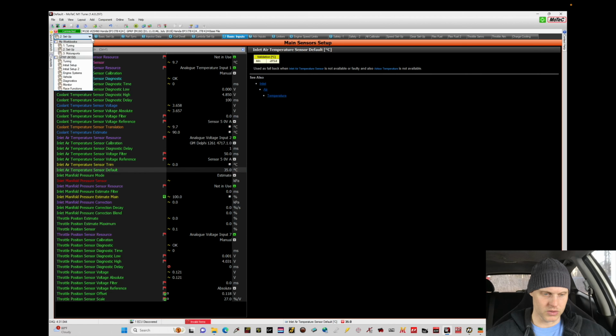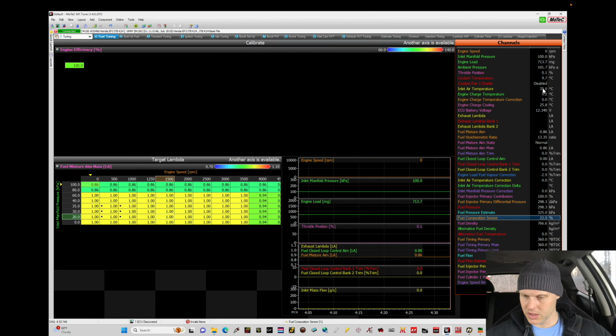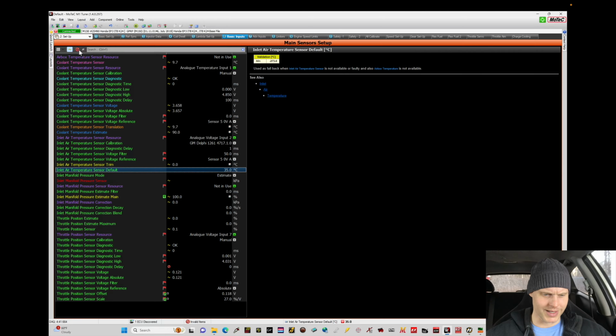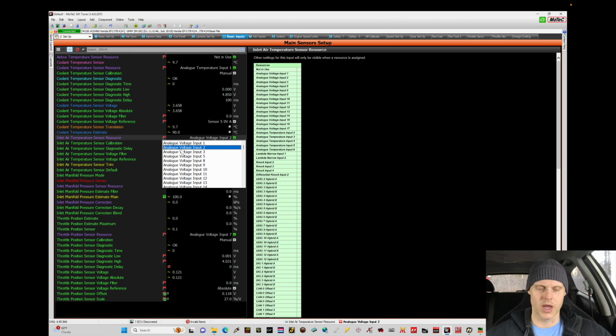Let's go back in here and look real quick. Let's go into tuning, back over to inlet air temp — it's showing 35 degrees Celsius. Let me check if it's on another input. I don't think it is. Here's the issue: I set it on analog voltage input, not analog temperature input, so I made a mistake there when assigning it. That's why it's not reading.